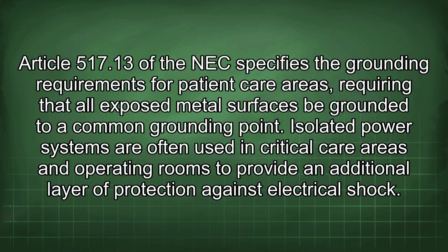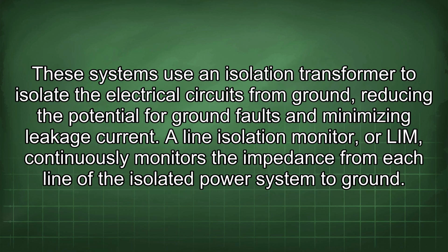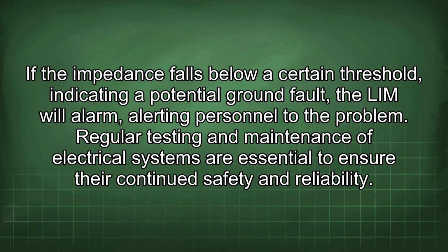Isolated power systems are often used in critical care areas and operating rooms to provide an additional layer of protection against electrical shock. These systems use an isolation transformer to isolate the electrical circuits from ground, reducing the potential for ground faults and minimizing leakage current. A line isolation monitor, or LIM, continuously monitors the impedance from each line of the isolated power system to ground. If the impedance falls below a certain threshold, indicating a potential ground fault, the LIM will alarm, alerting personnel to the problem. Regular testing and maintenance of electrical systems are essential to ensure their continued safety and reliability.